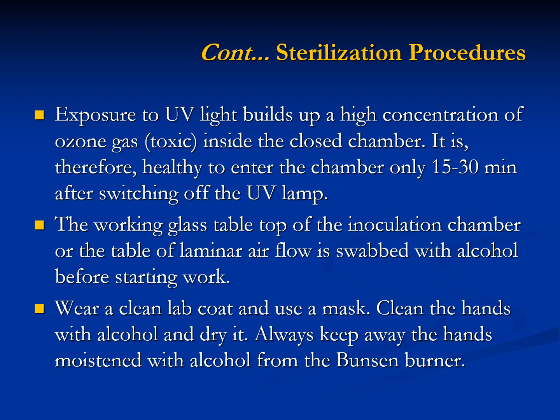Exposure to UV light builds up a high concentration of ozone gas, which is toxic inside the closed chamber. It is therefore healthy to enter the chamber only 15 to 30 minutes after switching off the UV lamp. The working glass tabletop of the inoculation chamber or the table of the laminar airflow is swabbed with alcohol before starting work. Always wear a clean lab coat and use a mask. Clean the hands with alcohol and dry them. Always keep away the hands moistened with alcohol from the Bunsen burner.